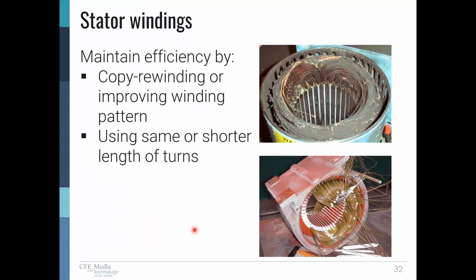The stator windings, copy rewinding. To maintain efficiency, we want to put the winding back and have it perform the way it was originally. This winding, if we look, you can see coils that loop around, and if you look closely, you can see where they go up and over inside. This means they have a common center, so it's kind of like an oval if you looked at it from left to right in the picture.